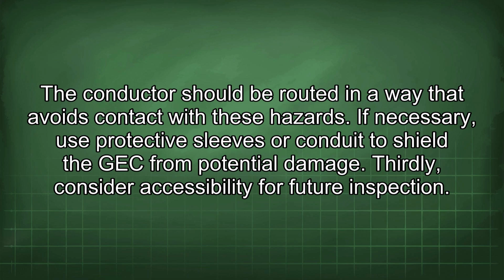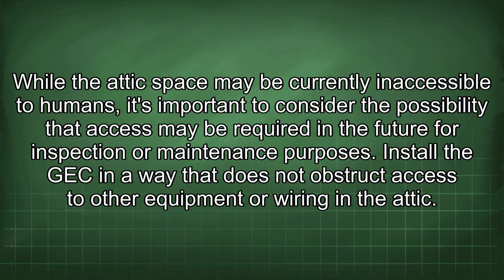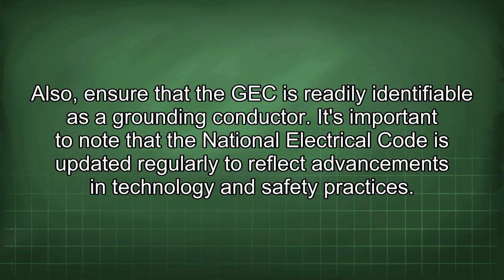Thirdly, consider accessibility for future inspection. While the attic space may be currently inaccessible to humans, it's important to consider the possibility that access may be required in the future for inspection or maintenance purposes. Install the GEC in a way that does not obstruct access to other equipment or wiring in the attic. Also, ensure that the GEC is readily identifiable as a grounding conductor.